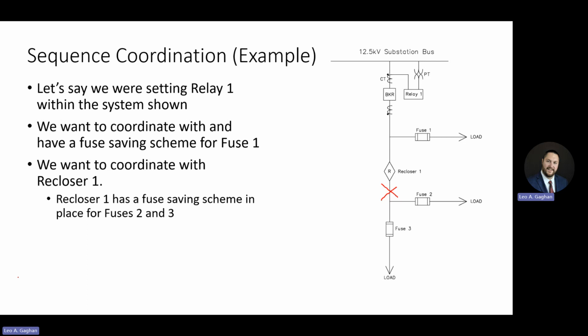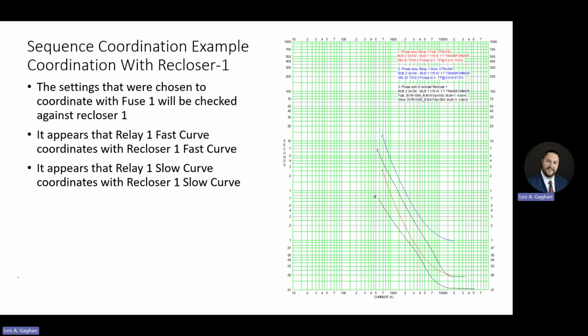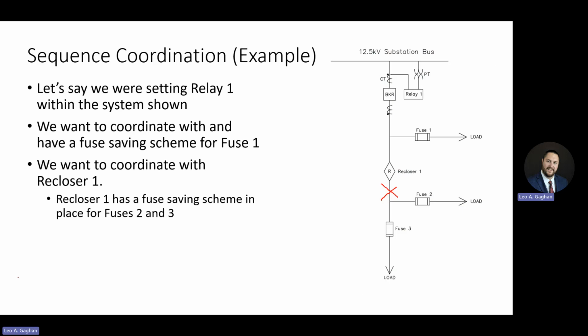But the basic principle here is, let's say we had a permanent fault on the X. Well, in that case, recloser 1 is going to trip on its fast curve, and then relay 1 is not going to trip, right? Which is good, because we don't want the load off of fuse 1 to lose power, and it can be isolated by the recloser. So that's a good thing, right? Recloser 1 tripped, the relay didn't. Now, eventually, recloser 1 is going to move to its slow curve, and unless we intervene, relay 1 is going to stay on its fast curve.